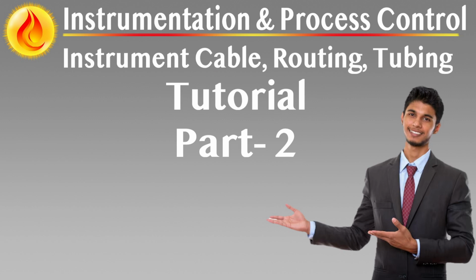All routing layouts must prioritize access for cable pulling, ensure bending radii comply with manufacturer's specifications, and support future capacity by including spare duct or tray space. Final routing design is subject to principal approval.